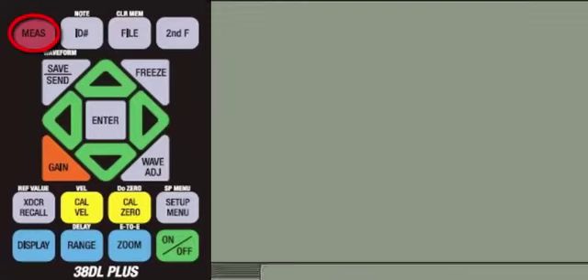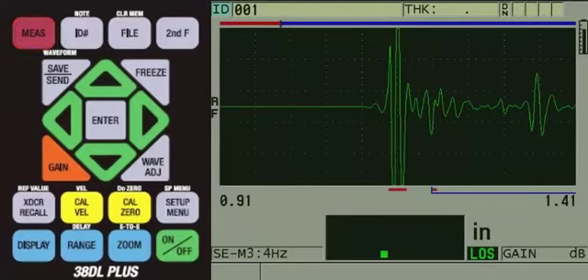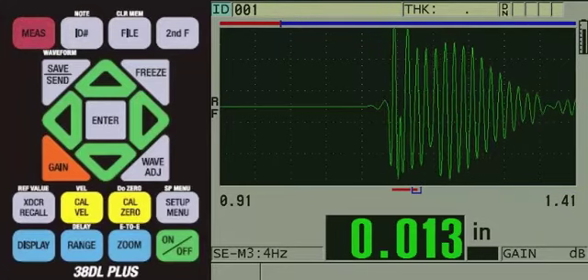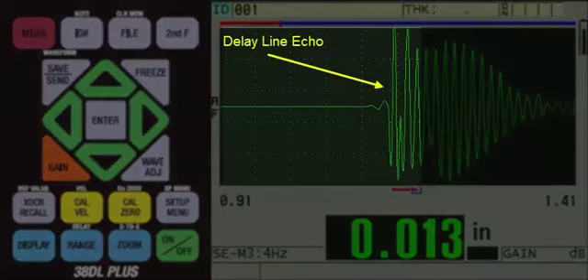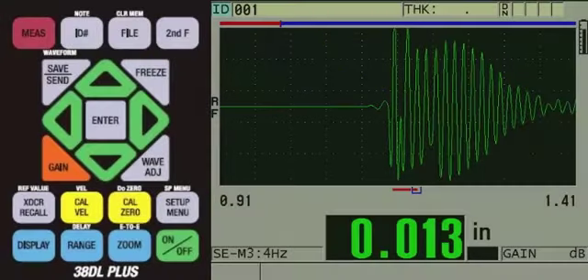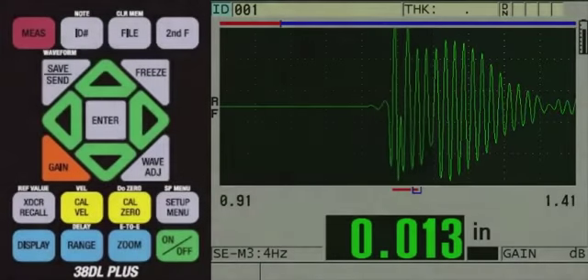We can now apply couplant to the part and couple the transducer onto the sample and pull down on the spring-loaded holder, so the part is seated in the V-notch. We begin to get a reading which appears to be correct. However, there appears to be some potential interference from the trailing edge of the delay line echo. Also, since aluminum is a good transmitter of sound, there are cleaner multiples further out in time, which do not have the potential to be interfered with by the trailing edge of the delay line echo.